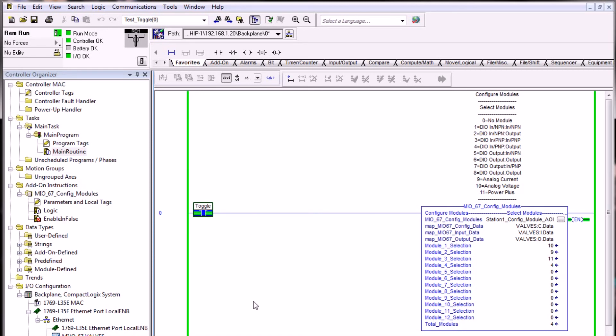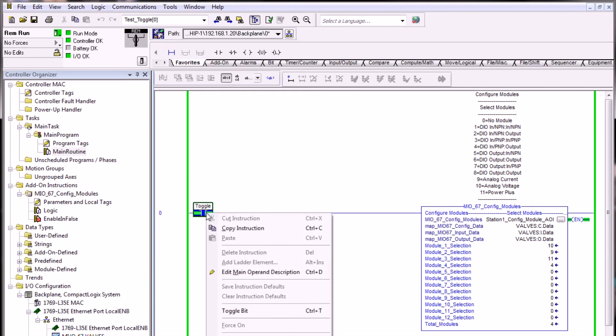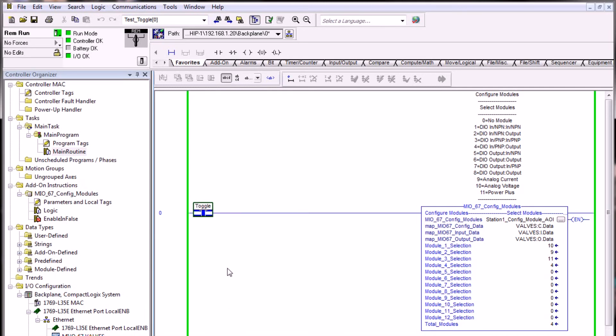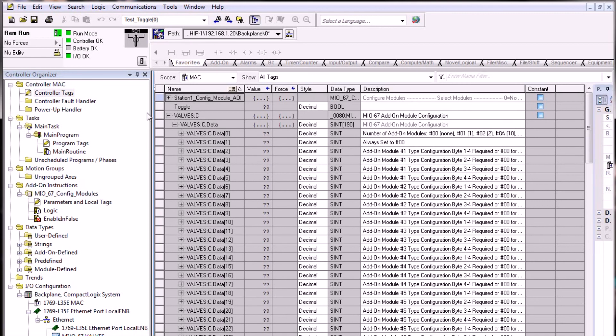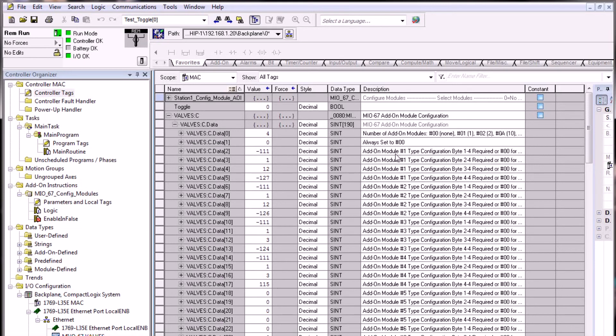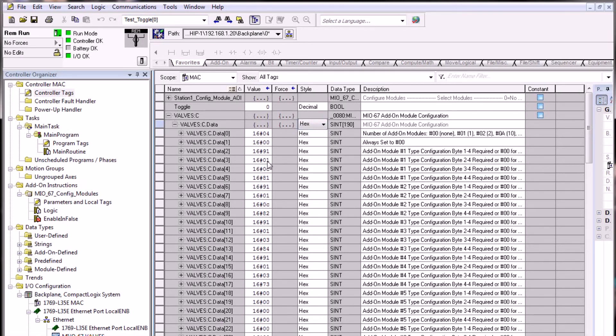Once we've written the configuration to the PLC config tag, we no longer need to enable this AOI — we can leave this rung false for the remainder of the project. We can go into the controller tags to confirm whether the configuration wrote. We can see values have been written in between add-on modules one and four. These values are shown in decimal by default, but we can select hex in the c.data view to change them to hex values, which should reference the same hex values in the UI173 manual provided by Mac.